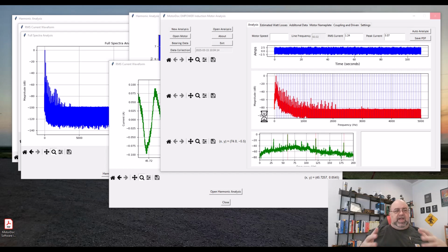So if I put in, say I have a really nasty, dirty ground because some marketing guy sold me that their drive is clean and meets IEEE 519, read my article on that lie, that kind of thing. 519 isn't meant for specifying an inverter, let alone a branch in your system. It's only meant for between you and the utility at the point of common connection.